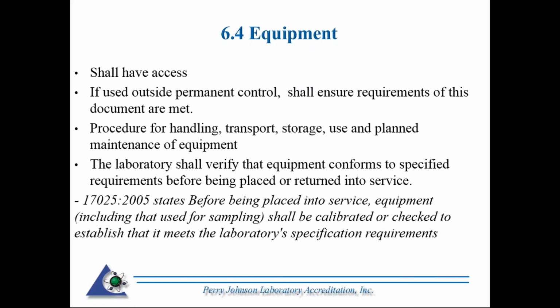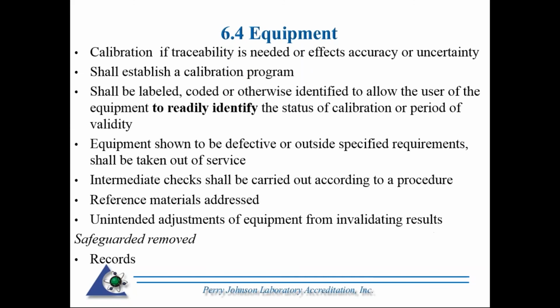2005 stated calibrated. But 2017, we dig a little bit deeper. It says you have to verify, and then it goes into specific examples of when you need a calibration as opposed to a verification. So, of course, measurement traceability, or if it directly affects accuracy or uncertainty, then of course you need to have it calibrated. As far as the type of calibration, it depends whether or not traceability is needed, and the accuracy requirements. And if you do have calibrations with your equipment as specified in 2005, you have to establish calibration programs.